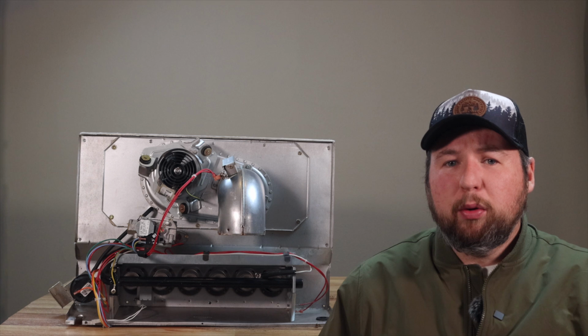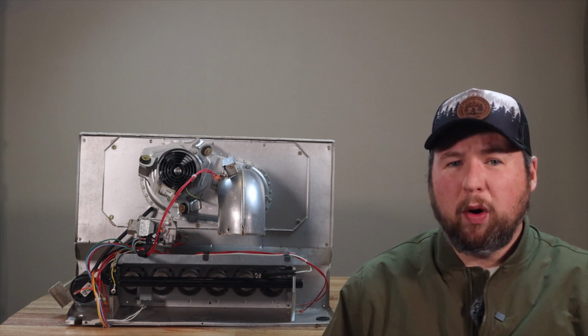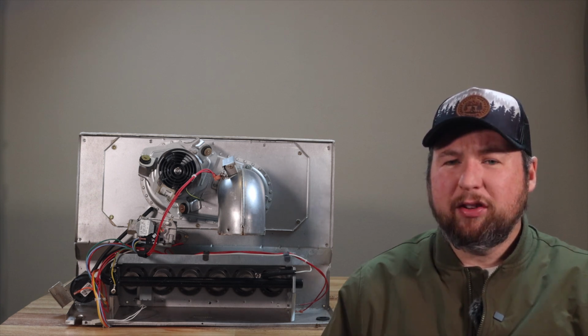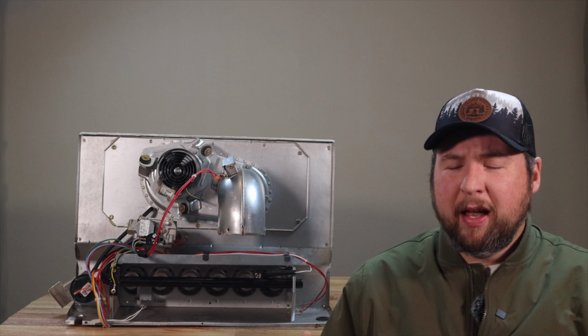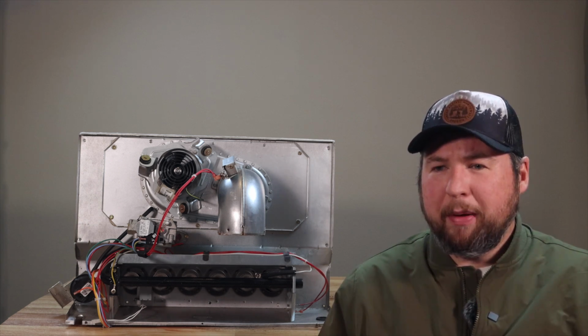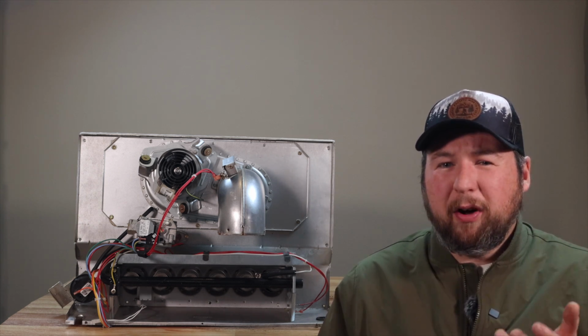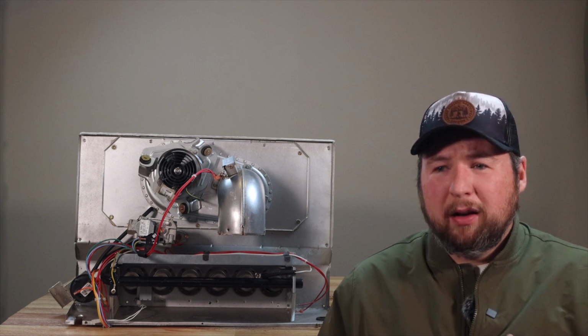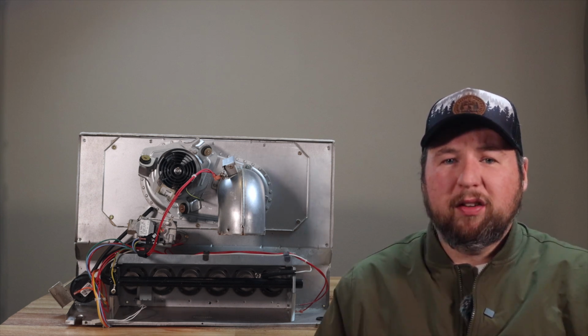And then you have the newer style. The temperatures are still pretty high, but they're not quite as high as that. And that's just because what ends up happening with the natural draft furnace is about 60% of all the heat it produces goes into the home. It transfers into the airstream.